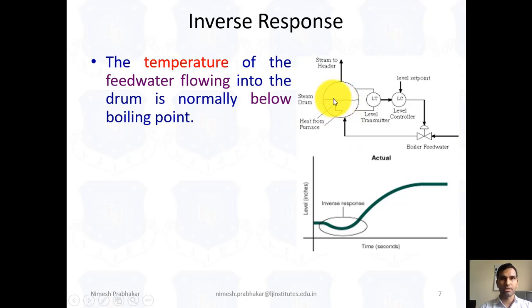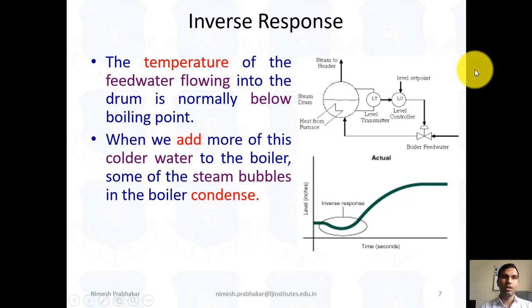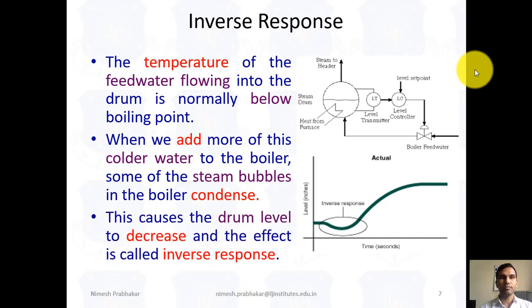Yes or no? Yes, of course. Because inside this drum the temperature of the water is higher than the temperature of the water we added. So when we add more of this cold water to the boiler, some of the steam bubbles in the boiler condense. This causes the drum level to decrease, and the effect is known as the inverse effect.